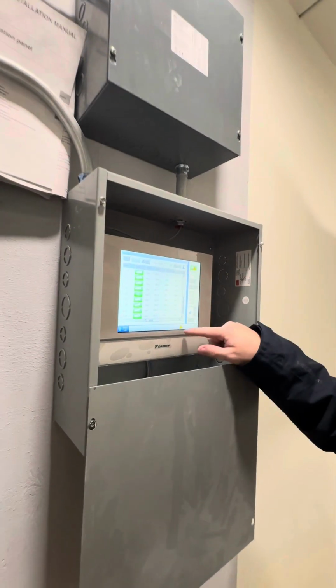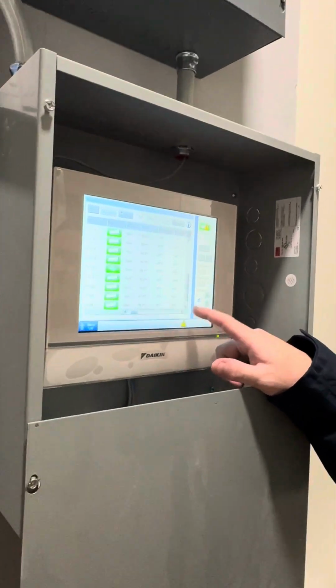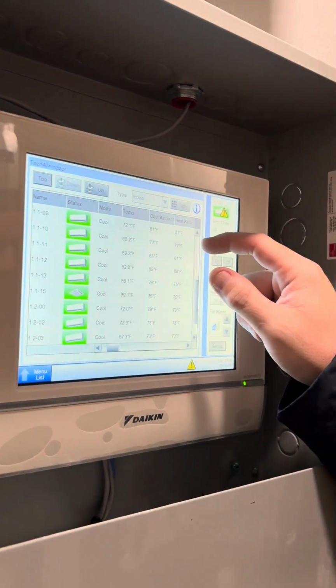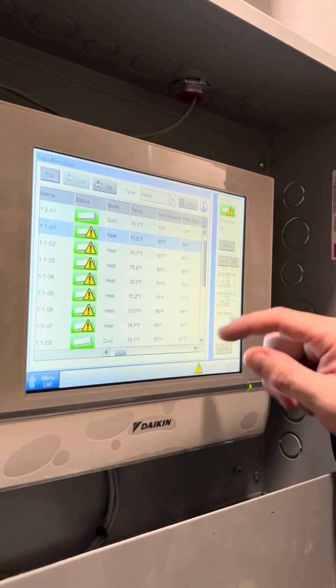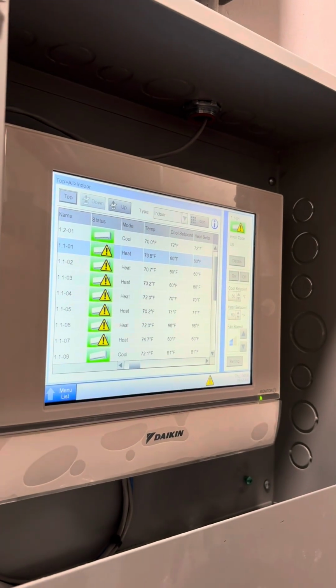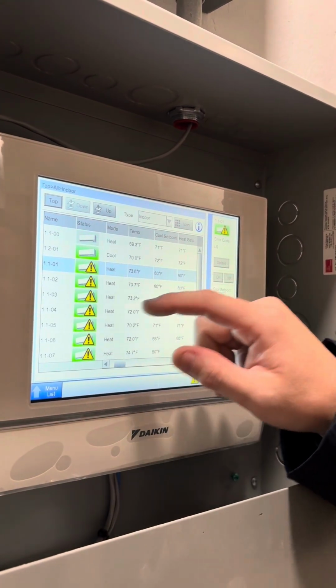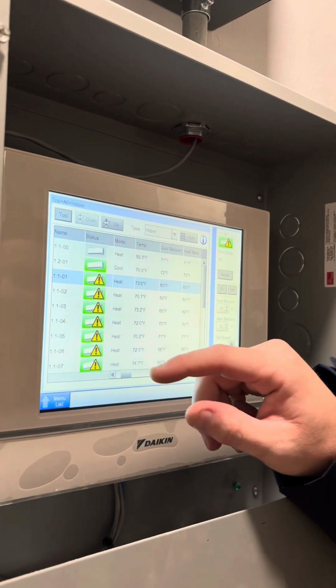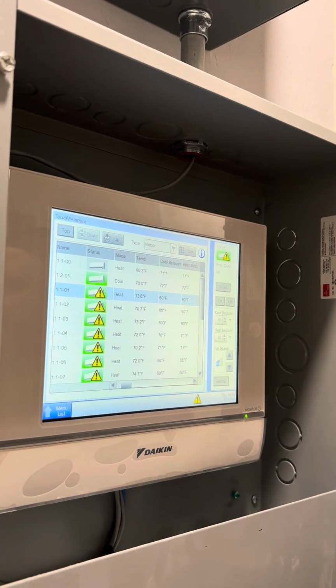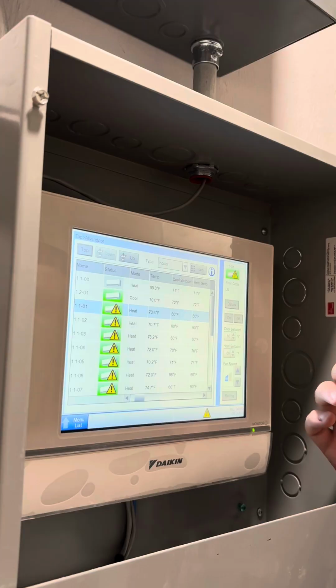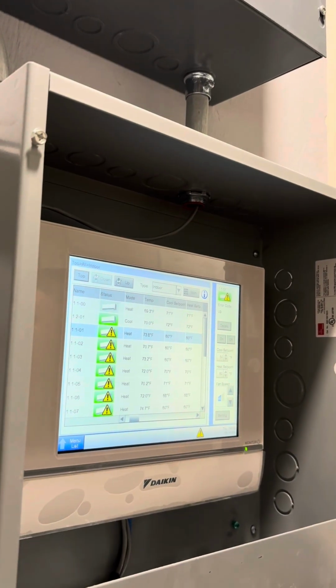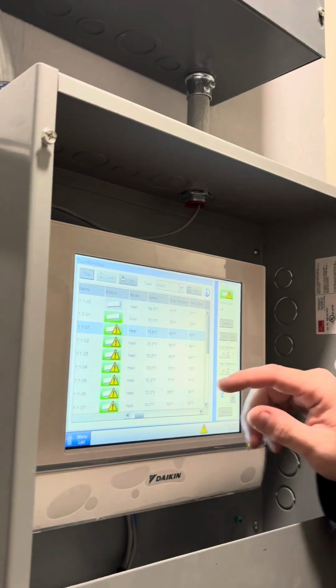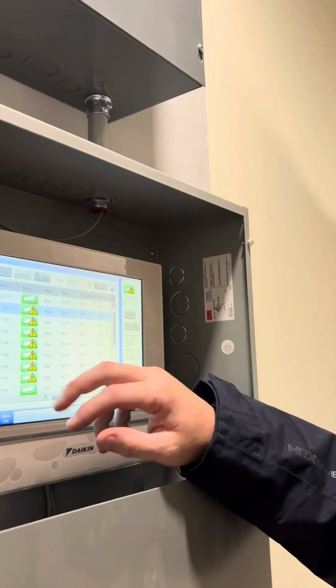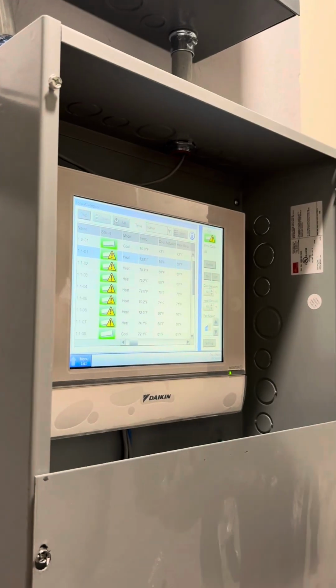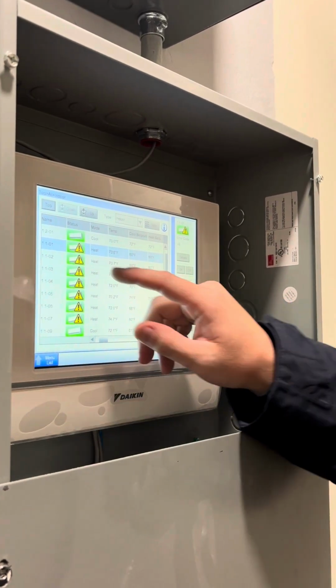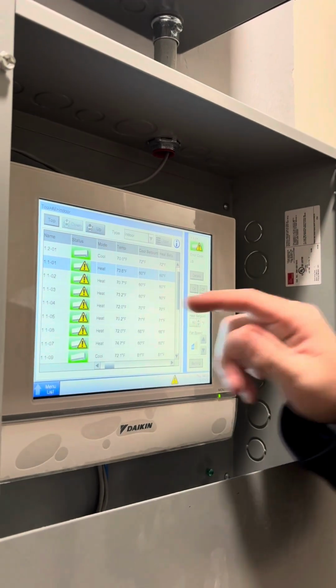So you'll notice that there's an error code, shown as a triangle. I noticed from when I was here earlier that it seems to be from the 3rd, 4th, 5th floor. I think they're painting those suites or something's going on there. With this U9 code, even a quick Google search for Daikin U9 will tell you it's a loss of communication between the indoor units and the outdoor units. So there's a possibility these suites had their units powered down for whatever reason, and it may just take time for them to start talking back to one another.